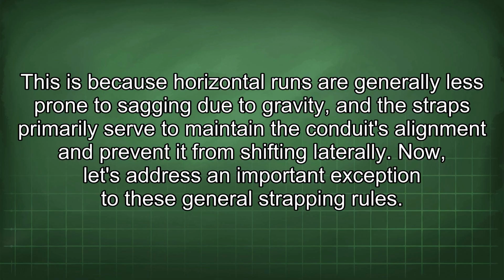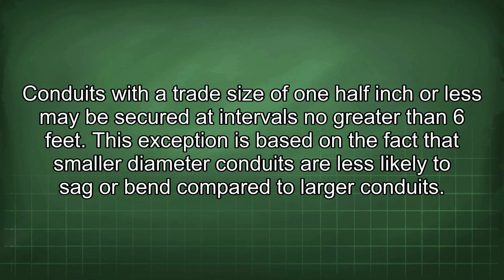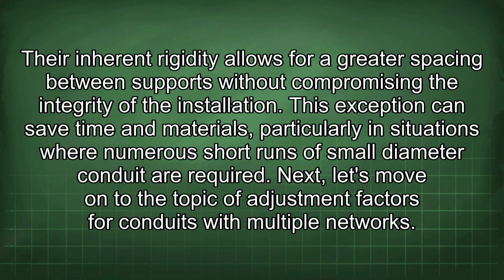Now, let's address an important exception to these general strapping rules. Conduits with a trade size of 1/2 inch or less may be secured at intervals no greater than 6 feet. This exception is based on the fact that smaller diameter conduits are less likely to sag or bend compared to larger conduits. Their inherent rigidity allows for a greater spacing between supports without compromising the integrity of the installation. This exception can save time and materials, particularly in situations where numerous short runs of small diameter conduit are required.